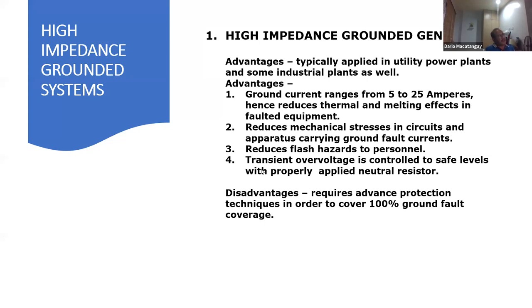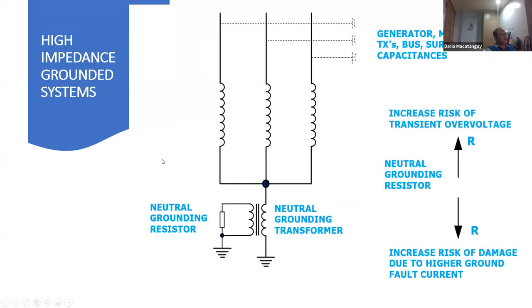The problem in a high impedance grounded system is that, without advanced technology, you can only protect up to 95% of the stator winding. But with the technology nowadays, they have developed the third harmonic protection scheme and the 20 hertz injection capability that we're going to discuss. Because of that, they can protect up to 100% of the stator winding. So let's look at the configuration of this one.